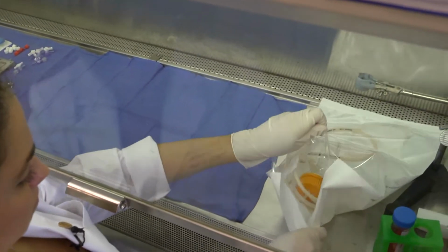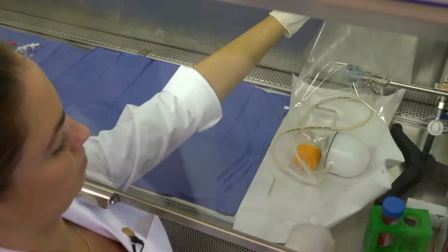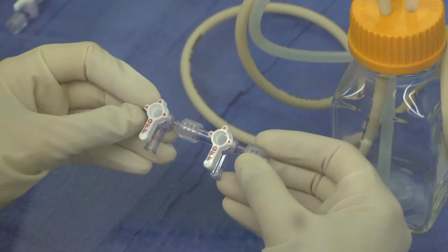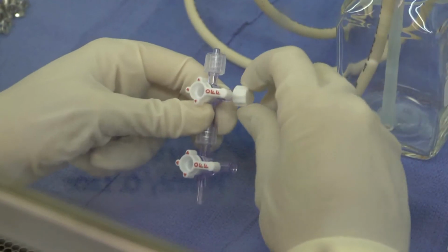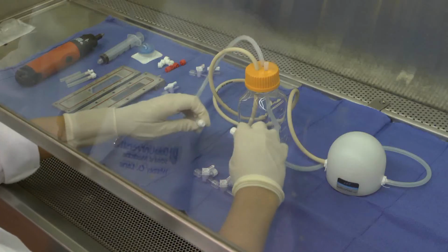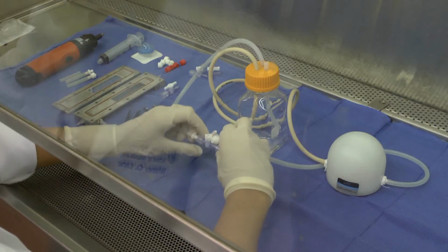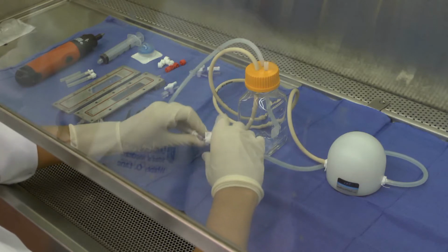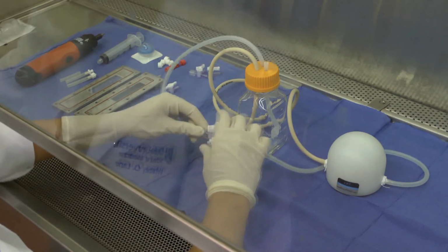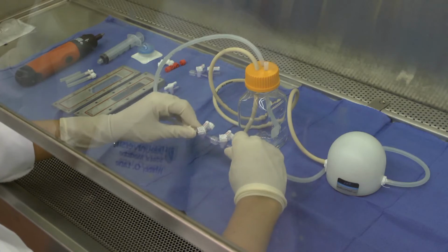Place the flow circuit, flow chamber, 4 4-way stopcocks, 1 1-way stopcock, and all the sterilized parts onto this sterile field. While wearing sterile gloves, connect the 2 4-way stopcocks. Place caps on the open sample ports. Detach the male and female Luer adapters attaching the 2 soft tubing segments of the flow circuit and insert the connected stopcocks.